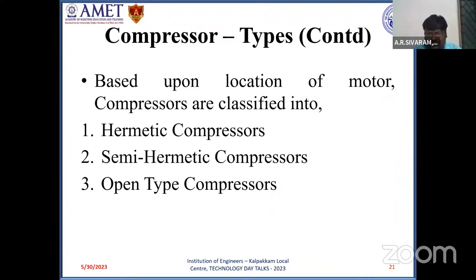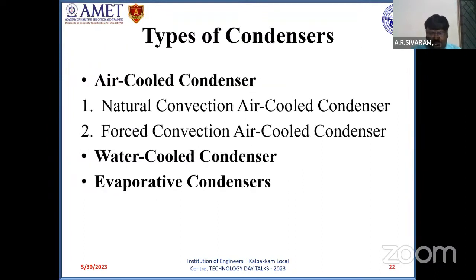Apart from this, compressors based upon location of the motor can also be classified as hermetic, which is nothing but closed type compressors. The rotary compressors which we employ for domestic fridges and ACs are actually hermetic type, which is completely closed. But the drawback of hermetic compressors is that if there is a problem with the motor, the only option is replacing the compressor, because opening the seal and repairing it makes the process more complex. So generally, when a problem occurs in hermetic compressors, we go for replacement rather than repair. The next type is semi-hermetic, and the next one is open type compressors.